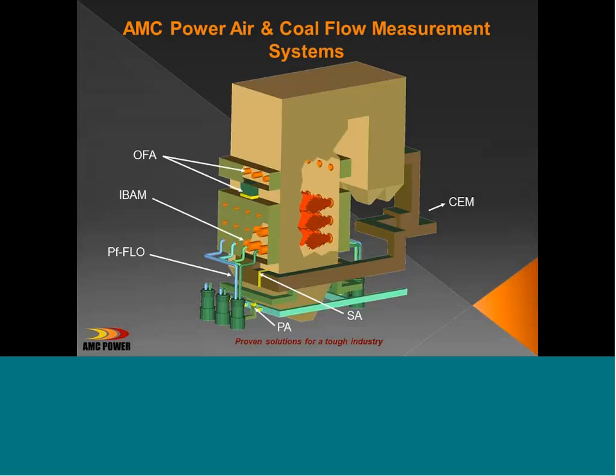Again, this is a boiler. I'm sure everybody here knows what this looks like. On the right where I show CEM, this is just pointing out that Air Monitor has been involved in CEM flow measurement. We also do primary airflow measurement, secondary airflow measurement, overfire air measurement, IBAM, which is individual burner airflow measurement, and now PfFLO. The reason for the boiler schematic, over on the right where the CEM is, you all know that you measure O2 on your boilers, and you control how much air goes to this boiler through that excess O2 measurement.